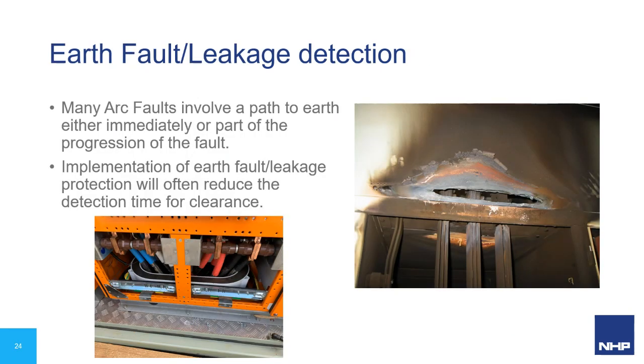Okay, so moving on to some of the mitigation strategies here. Many arc faults involve a path to earth, either immediately or as part of the progression of the faults. On the right-hand side there, we've got an arc fault which actually chewed through most of the switchboard. So quite simply, if you implement earth fault or earth leakage protection, you'll often reduce the time for clearance because earth fault is a lot more sensitive than your overcurrent short circuit protection that's usually in place.